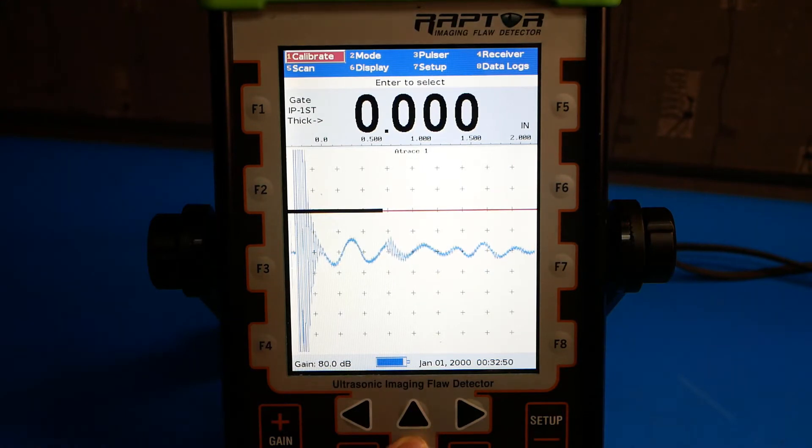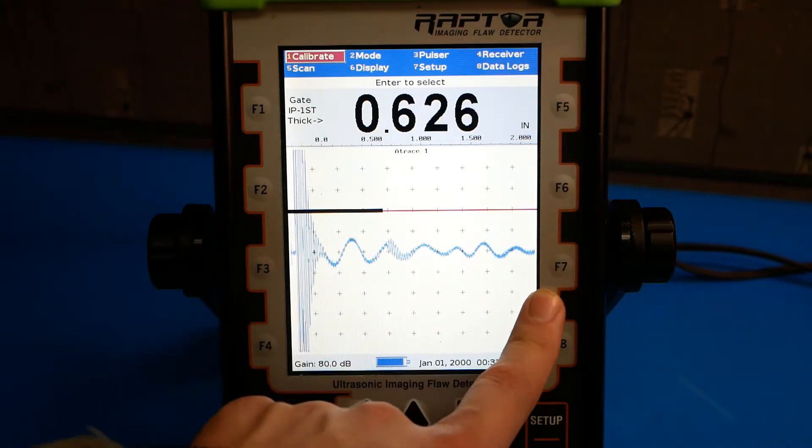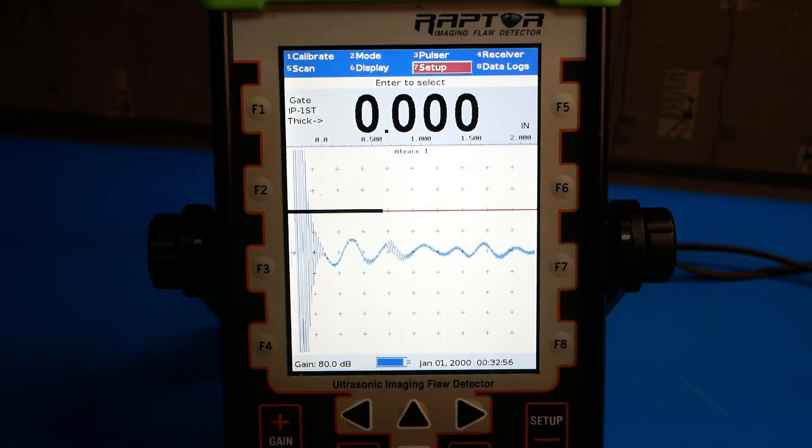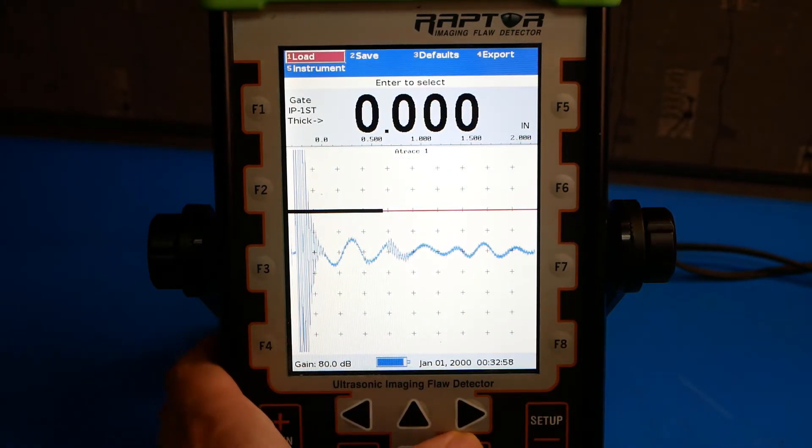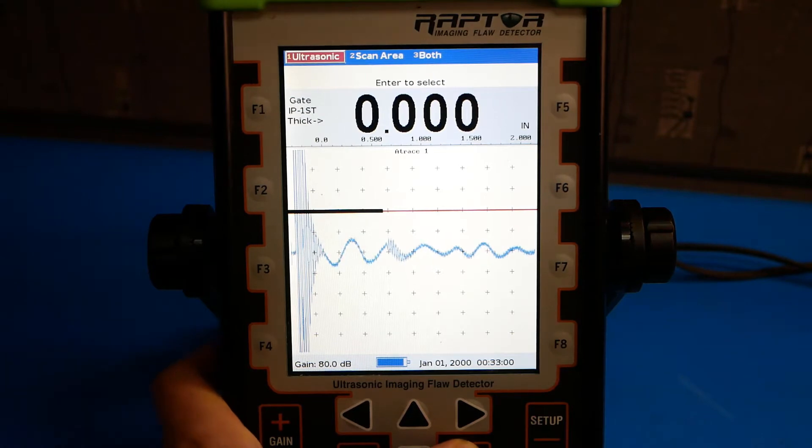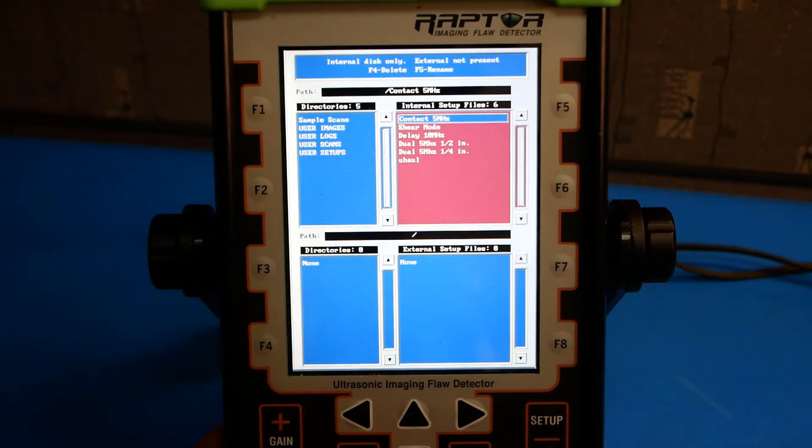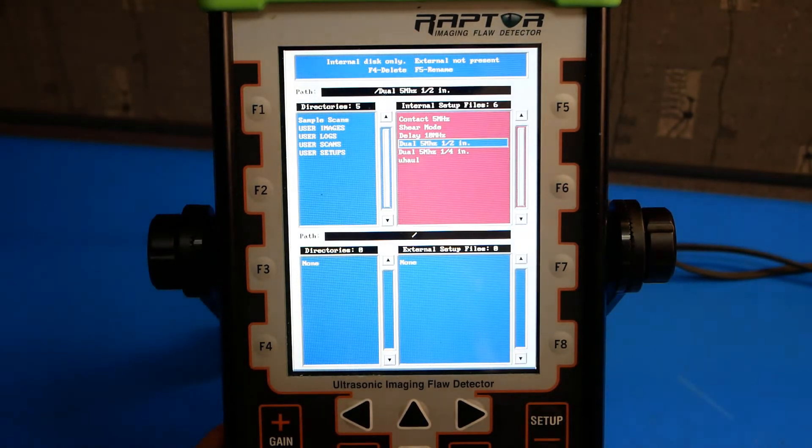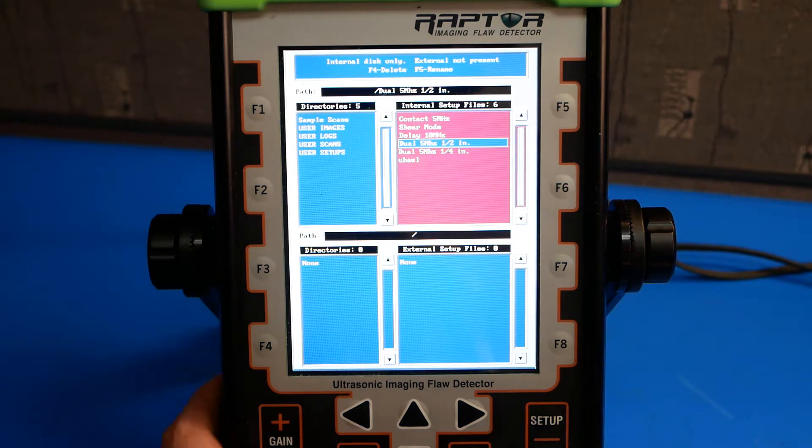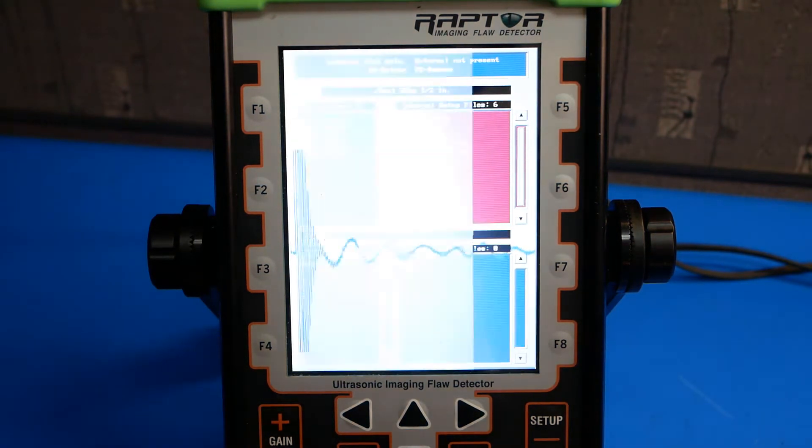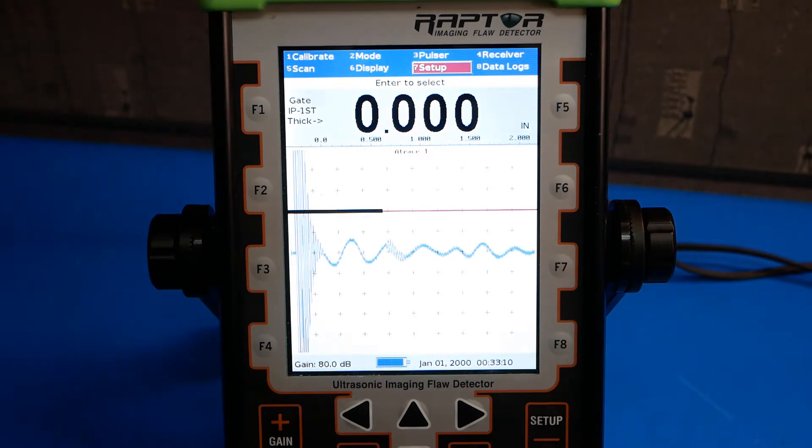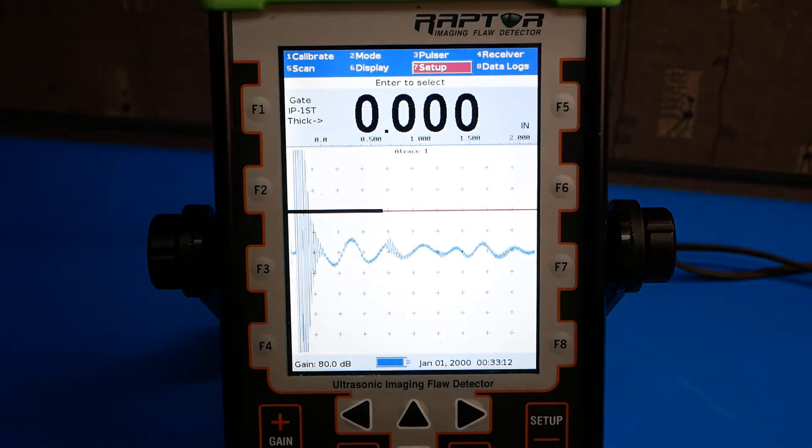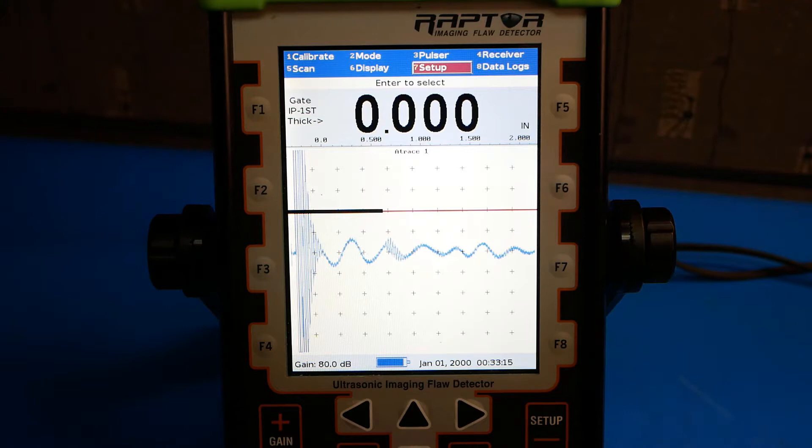Using the arrow keys or the scroll wheel or the function keys along the sides, navigate to the setup option. Select load, ultrasonic, and select the dual 5 MHz 1/2 inch probe profile. This will set up the gauge for most of the functions that we'll be using with the RCA 053 dual element probe.